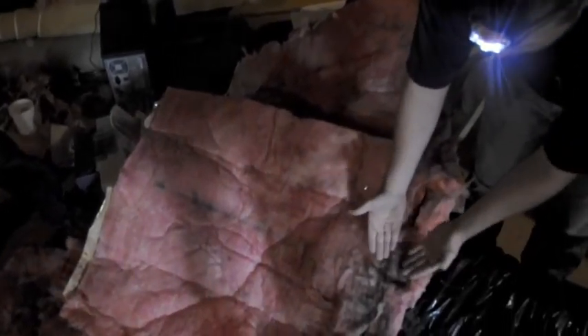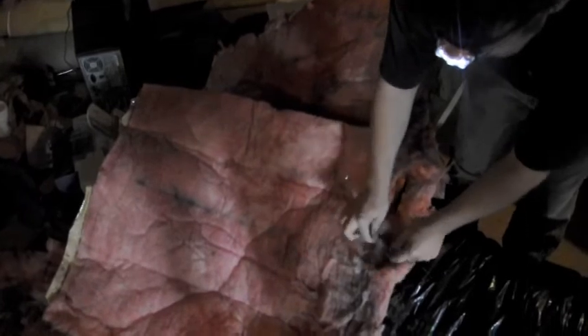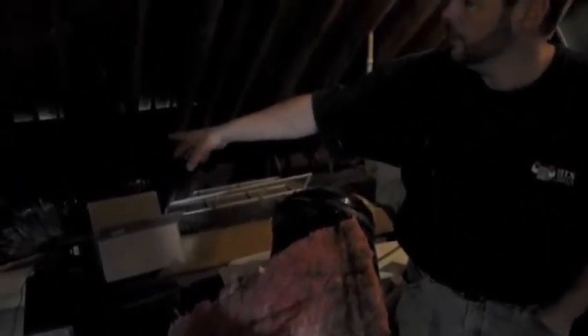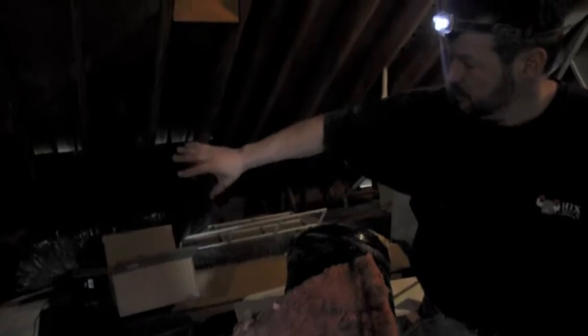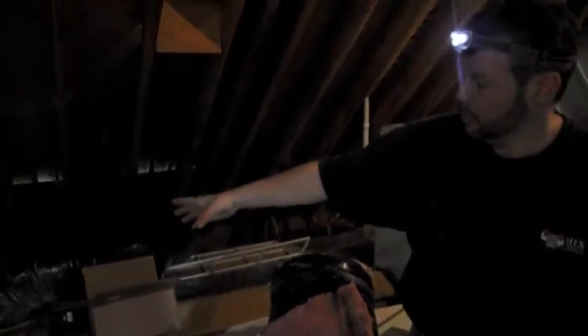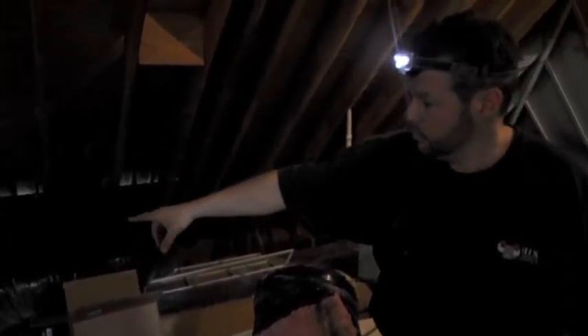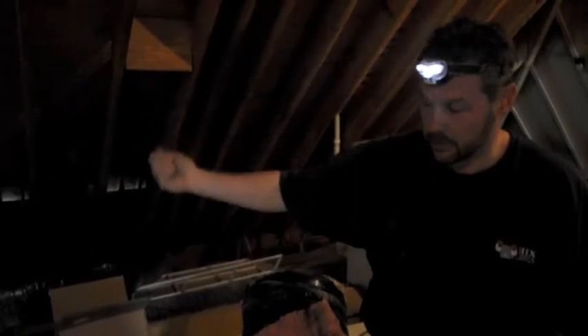It was not sealed, so when the air is passing through the duct, it is actually pulling in particles of fiberglass and also showing you where the dirt is entering into the duct stream. So we actually stripped that off. We redesigned the way the airflow comes out, and what that does is give you better airflow, better static pressures in your airstream, and we are actually sealing the ductwork from the inside so we will not have any more air leaks in the system.